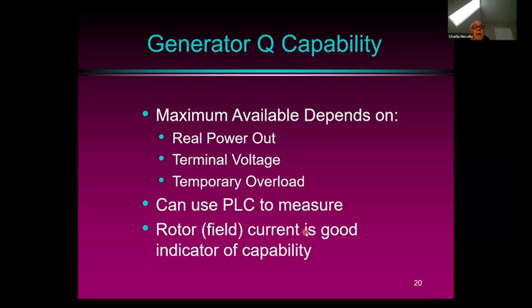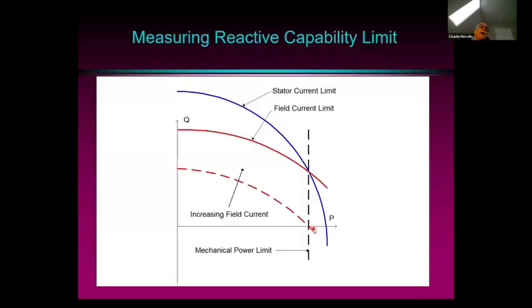The field current in the rotor of a generator is a good indicator of how close it is to its limit. So we have here the reactive power from a generator. We see that normally it would be operated in this area here, close to 0 reactive power output. But if reactive power is needed from the generator, it can go up to its limit. The field current on the generator normally would be the limiting factor, although closer to a power factor of 1, the stator current limit may be more important. But if you measure the field current going into a generator, you can tell how close it is to its reactive power limits.